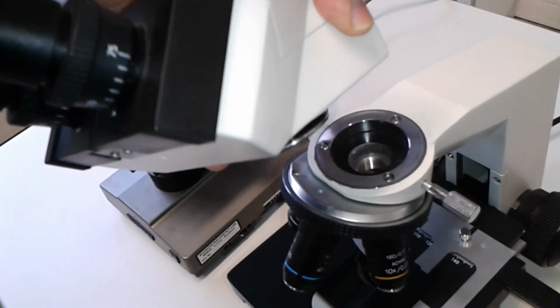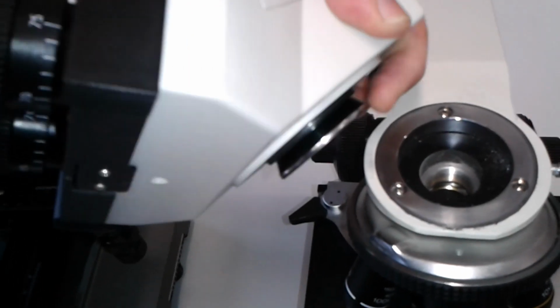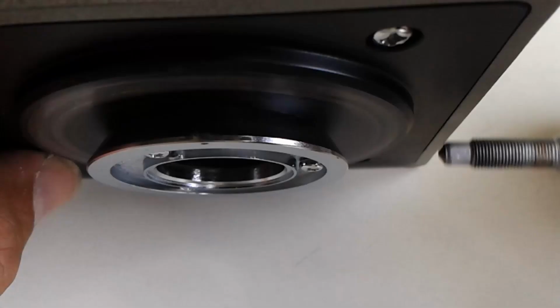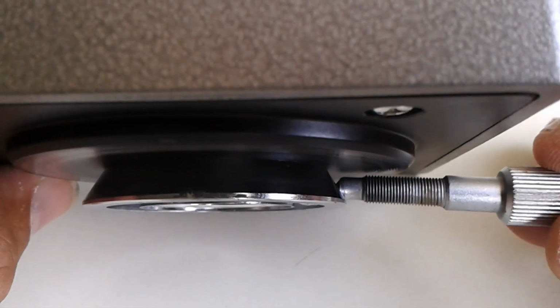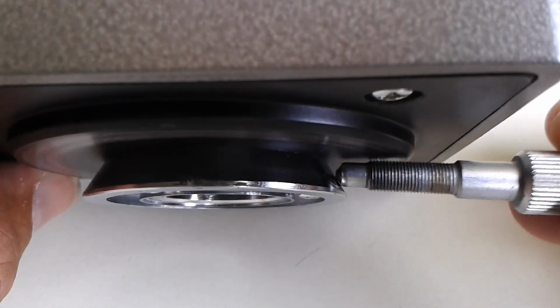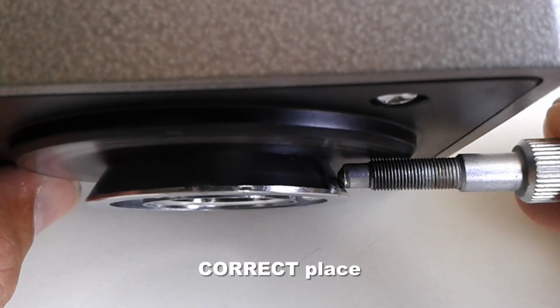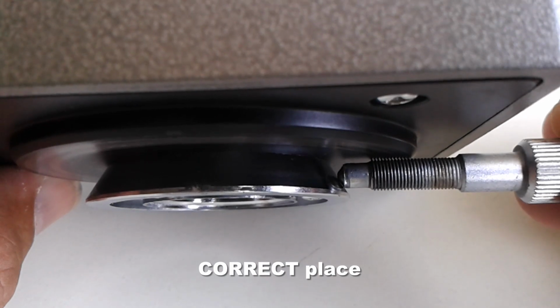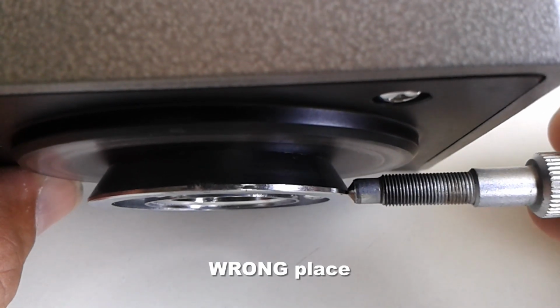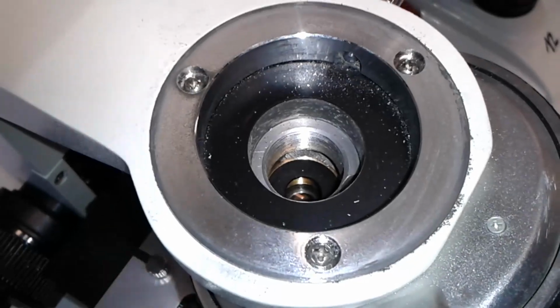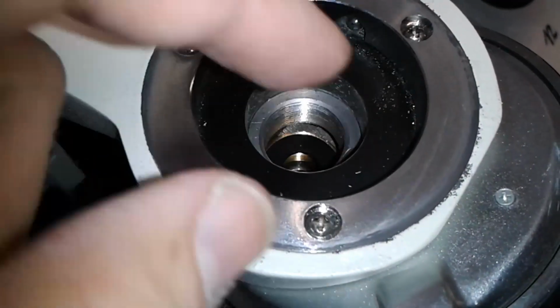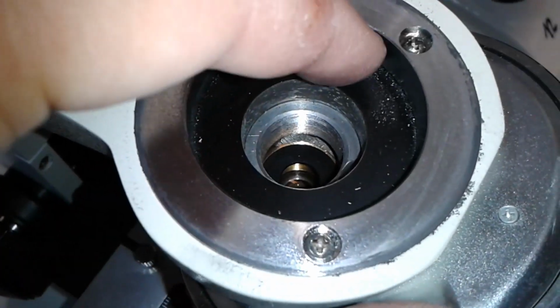And it was therefore not able to retain the microscope head, so it did not go into the so-called dovetail. Here, this is an example. This is the way it should be. The screw of them should actually go into the dovetail, but it did not, and it simply touched the dovetail on the edge. And this caused a lot of abrasion, and therefore there are a lot of metal filings inside the microscope because of the aluminum which got rubbed off.